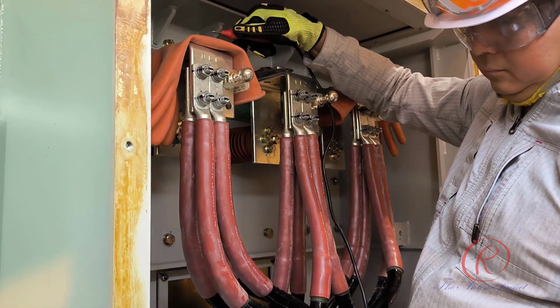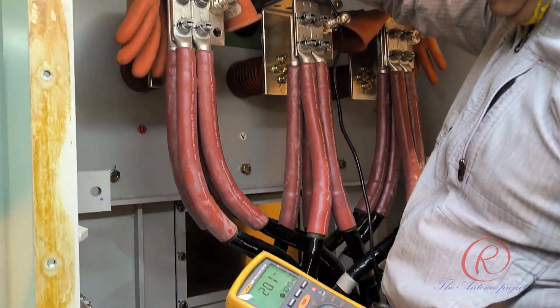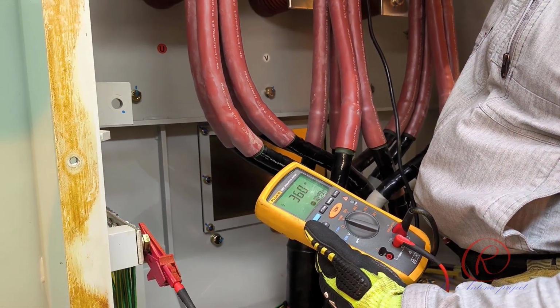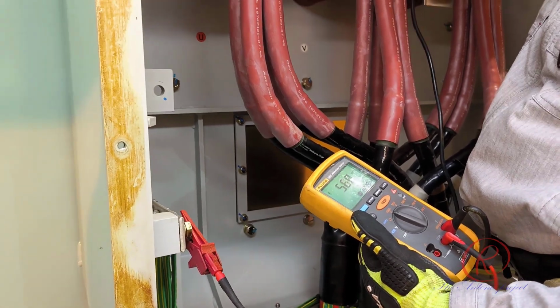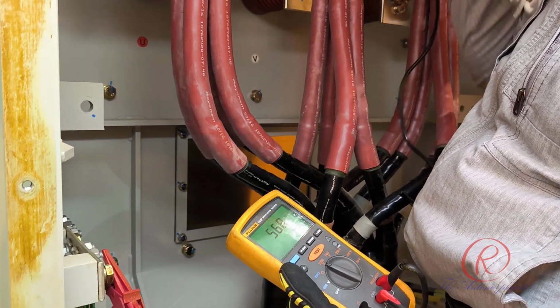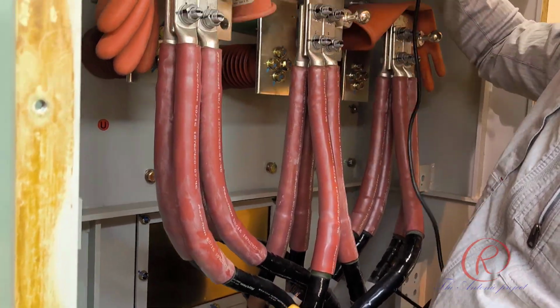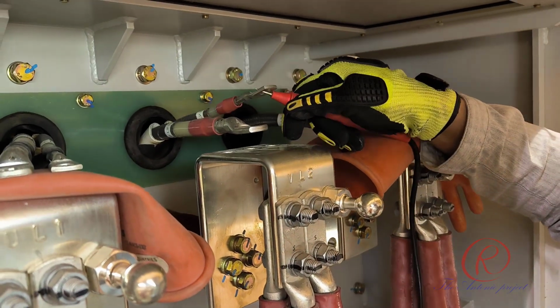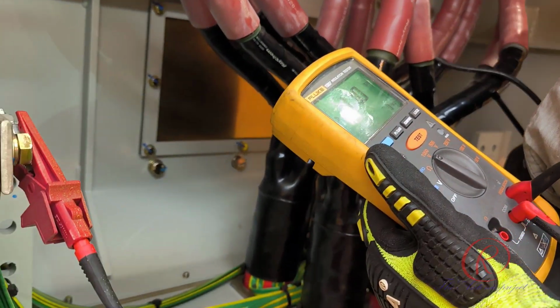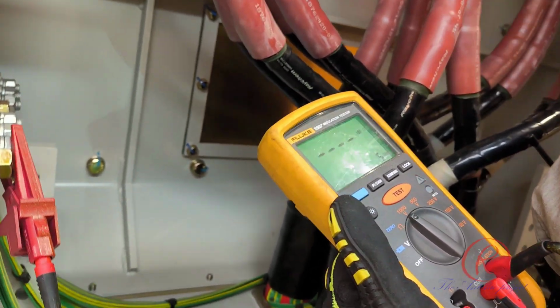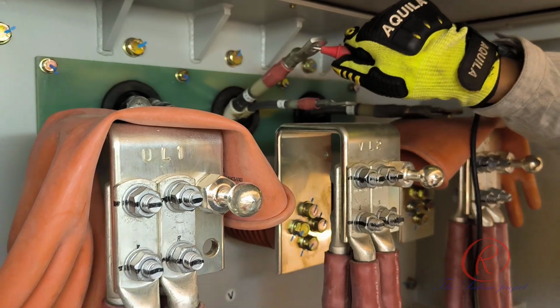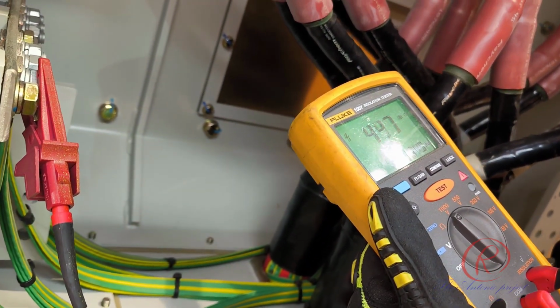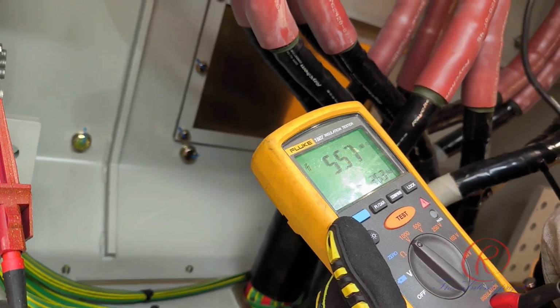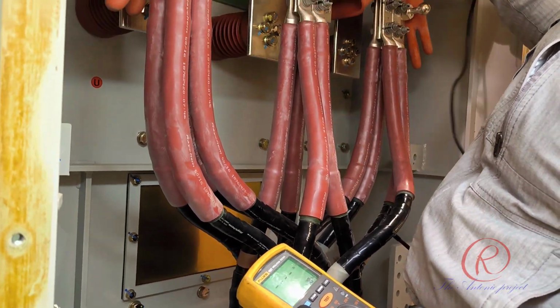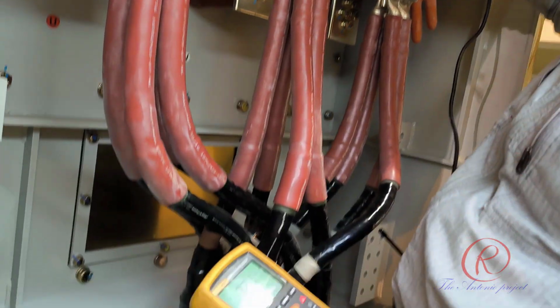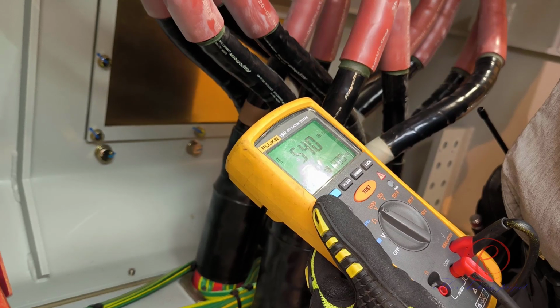The purpose of the insulation resistance measurement is to measure the resistance of the insulation materials used in the alternator windings. By measuring the insulation resistance, we can determine if there are any faults or deterioration in the insulation, which could lead to alternator failure or electrical hazard. It helps in identifying potential issues such as moisture ingress, contamination, or insulation breakdown. Regular insulation resistance testing is recommended to prevent unexpected alternator failures and ensure the longevity of the alternator.